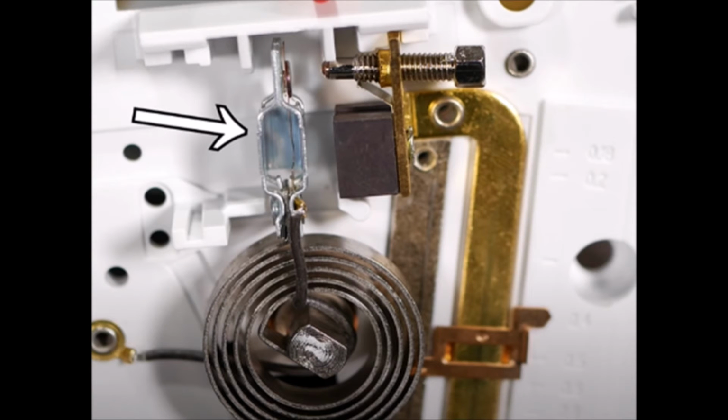If you see the picture here, specifically this is just a heating unit. More or less all that happens is that as the ambient temperature gets cooler, the strip will actually contract. But what this will cause is, because of the way it's wound, it'll cause the strip to move to the right until it hits that contact, and it'll close that contact, which will turn your heat on.